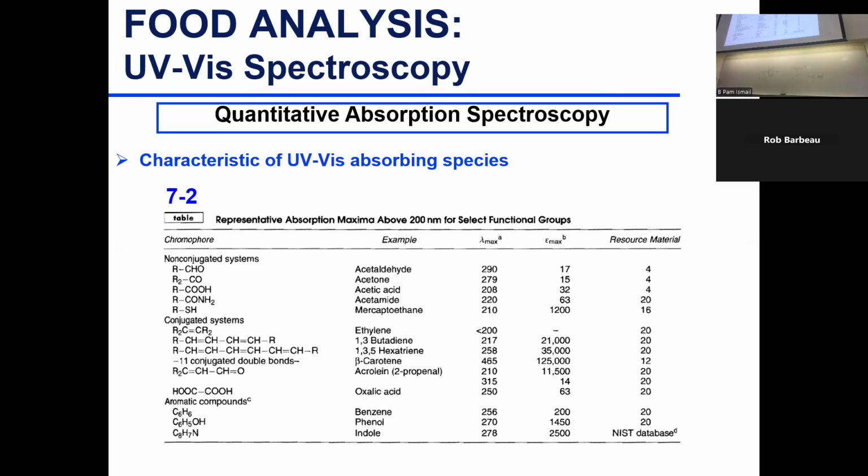Yes, for the double beam, you lose some light, because the beam of light is split into two, one going to the reference and one going to the sample, so less light intensity is reaching. So you lose a little bit of sensitivity, and you adjust your concentration accordingly.